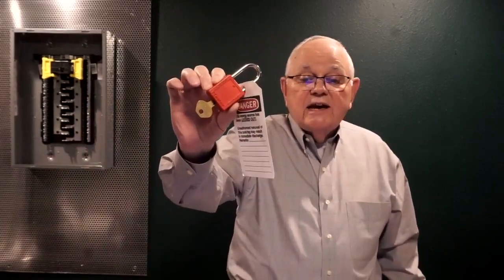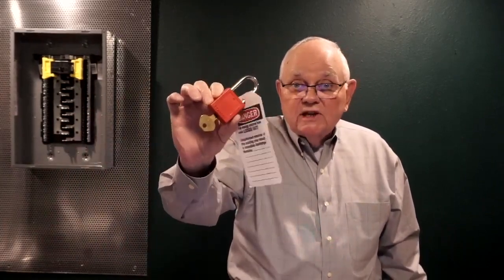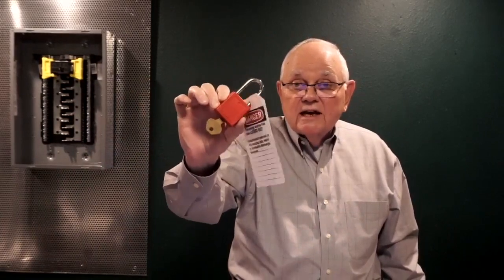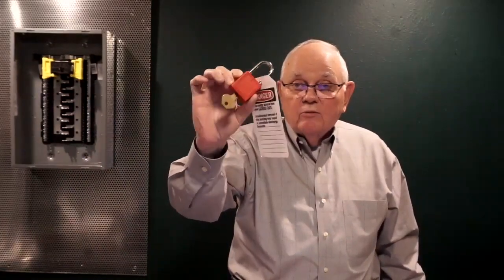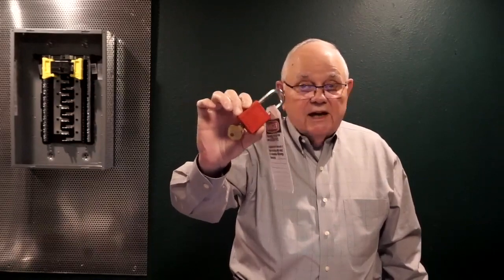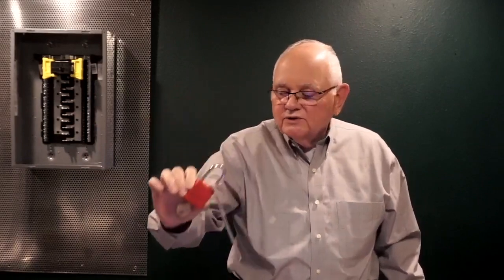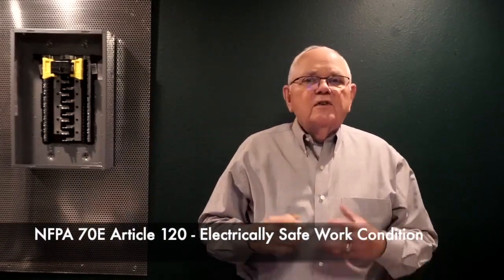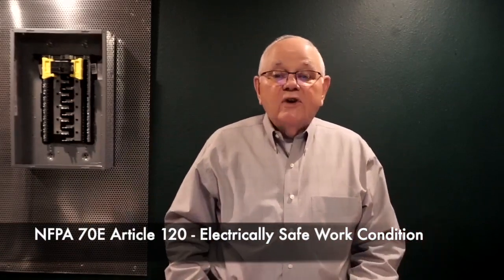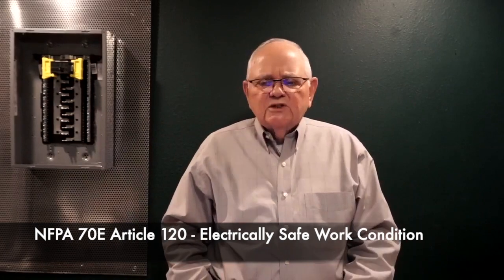So let's take a look at how we can do that. Probably, you know, in the best way, right here, isn't it? Lockout, tagout. Create an electrically safe work condition. Lock out and tag out the circuit, the equipment, and make sure it's de-energized. And that includes all sources of power, capacitors discharged, and so forth. So anyway, in NFPA 70E Article 120, that gives us the 8 steps in order to create an electrically safe work condition. So lockout, tagout is always the best way to go.